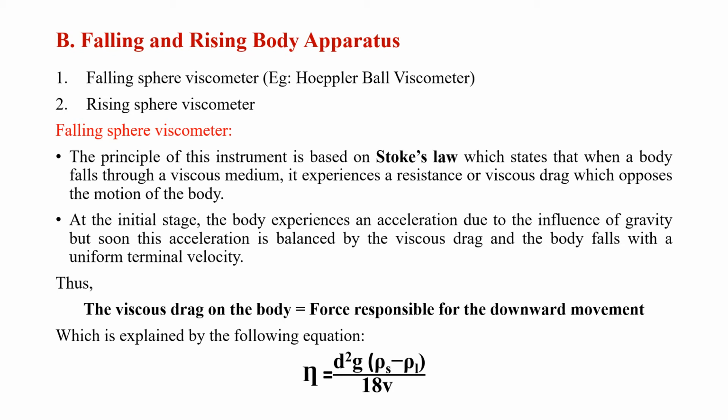Now let's see what actually happens in this instrument, the falling sphere viscometer, and how it really works. Keeping in consideration the example that was quoted before, the working principle is based on Stokes' law. Hope you all remember Stokes' law, which we discussed in the rate of sedimentation.